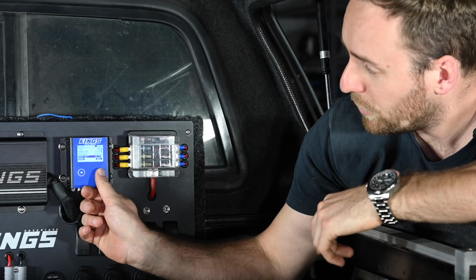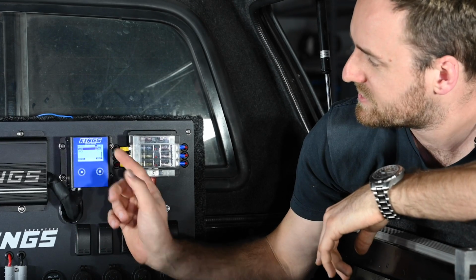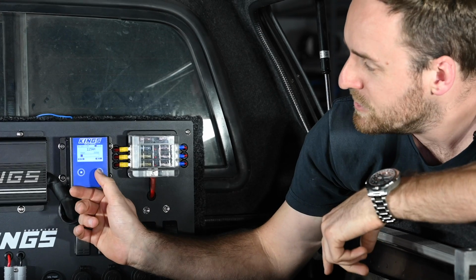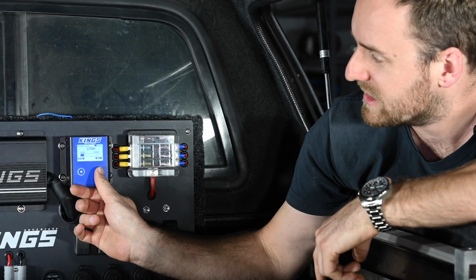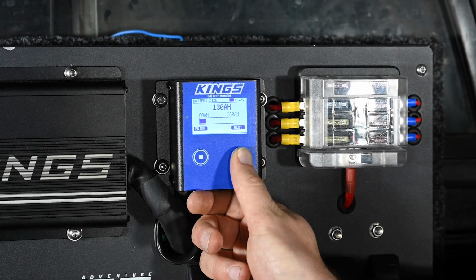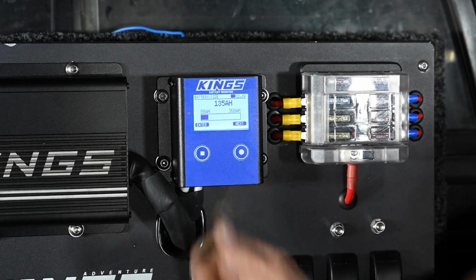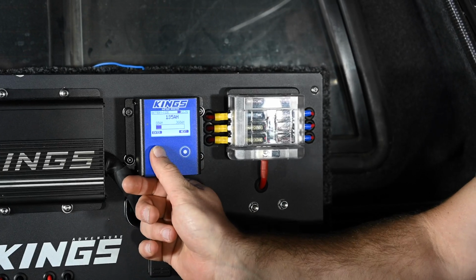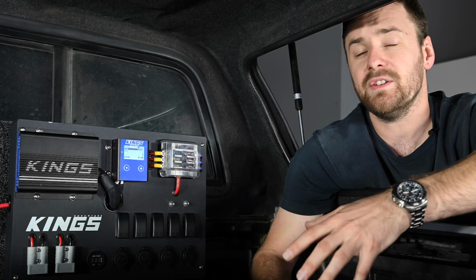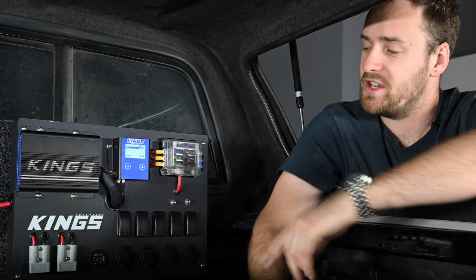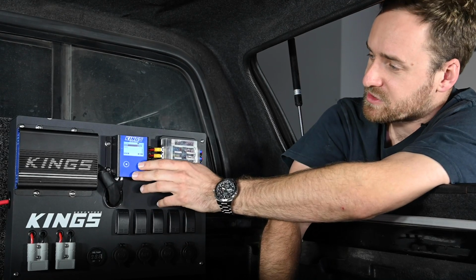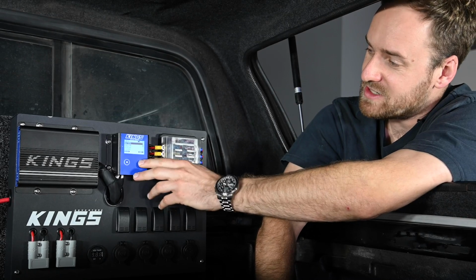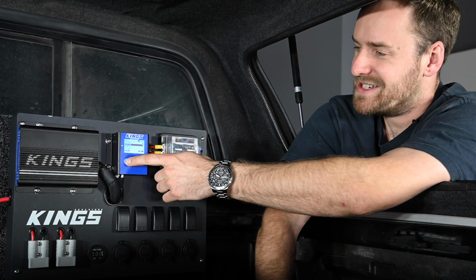point. Scrolling down from there, you've got the battery size. Now in this setup, I'm using a 138 amp hour battery. I'm going to select 130 as it's the closest number that's under my battery capacity, so it's not going to overestimate my power. So now that you've set the battery and voltage settings, you can go to the next menu item by scrolling down to back, then scrolling down to monitor and hitting enter.